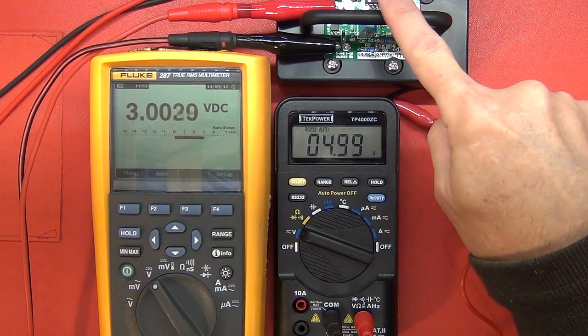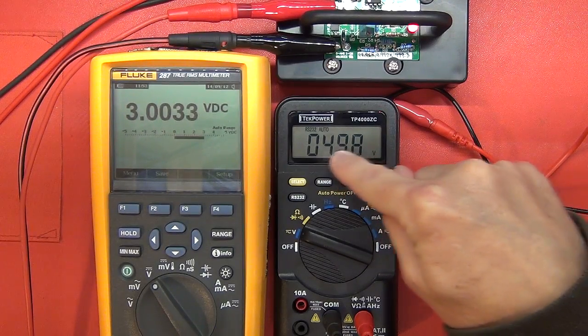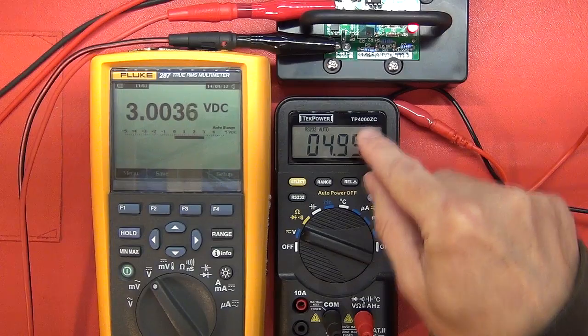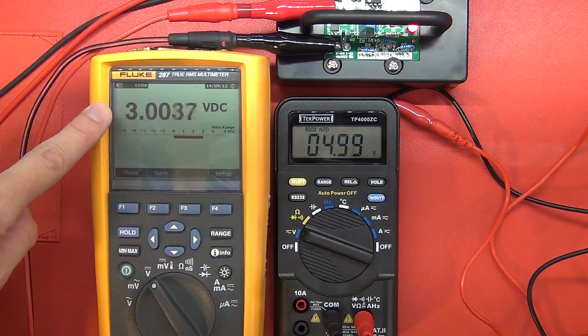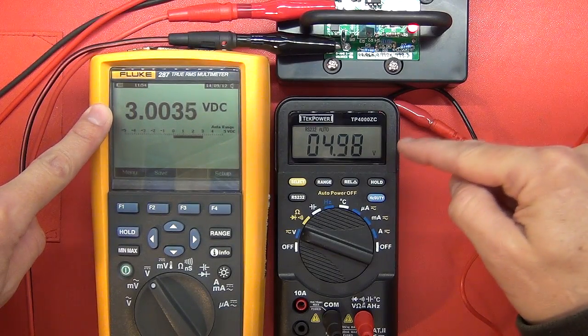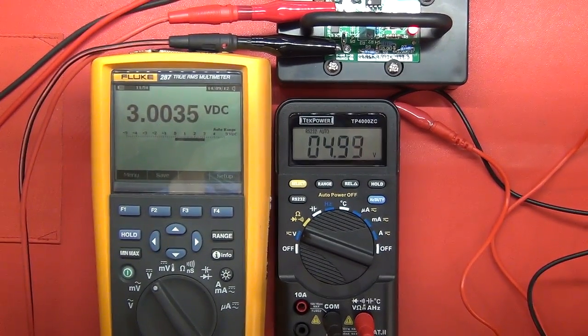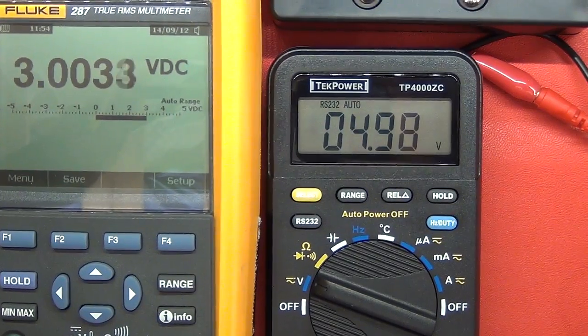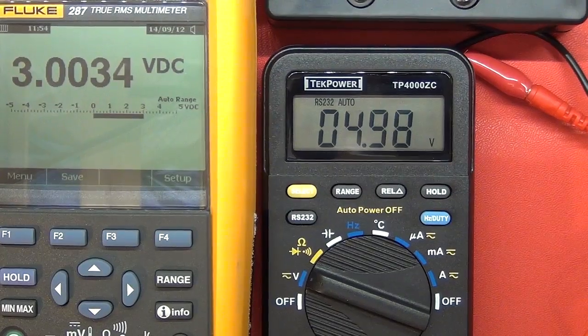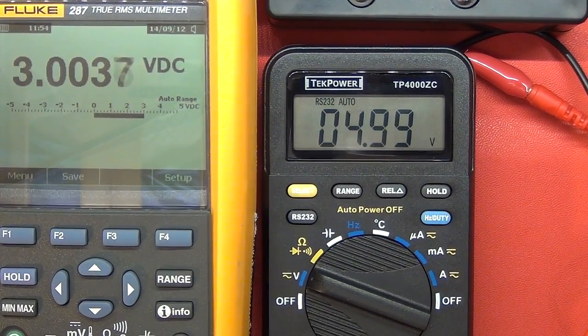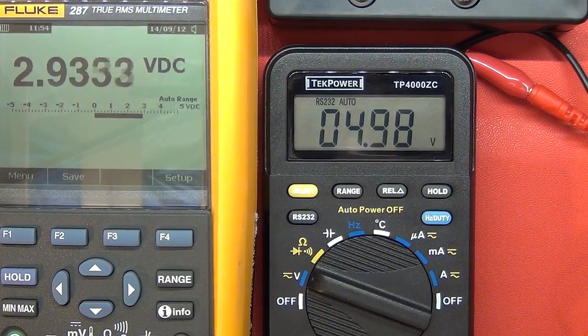Right, so the first test I'm going to do is to check whether the low battery warning on this comes on adequately before the readings go out. So, what I've got, I've got it connected to my 5-volt reference. So, basically, we want to ensure that it maintains a stable reading right until the point when the low battery warning comes on. My Fluke 287 here is measuring what the power supply is feeding it, because I'm obviously feeding it with my variable power supply. I'm going to drop the voltage to see how well that works. What I'm going to do, I'm going to bring you in closer so you can have a look at both those displays. In particular, what we want to see is the annotation, when the annotation comes on. So, I'm going to start dropping the voltage. I think in the instruction manual it says around 2.4 volts.